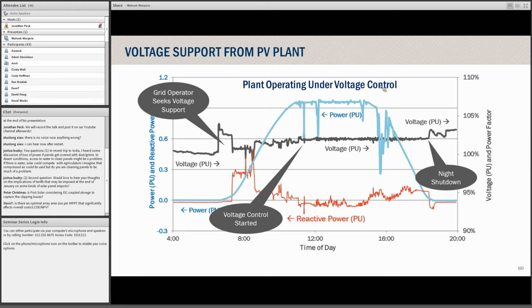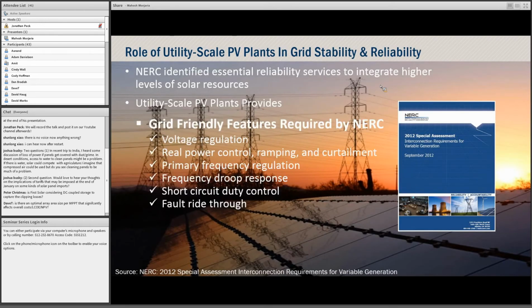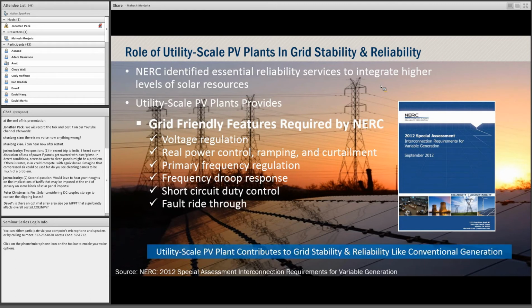So the most important thing I'm saying is that we built in the ability to control the voltage, and we are able to show that this is actually doing that. And at night, of course, the plant shuts down and the voltage starts fluctuating again. But power electronics can be used to even control voltage at nighttime. Anyway, the bottom line is we build all these plants with this kind of capabilities of voltage regulation, real power control, etc. And these are all the grid-friendly features that are required by NERC for a plant. And so indeed the utility scale plants, unlike rooftop PV or some other PV plants, they do contribute to grid stability and reliability like conventional generation.